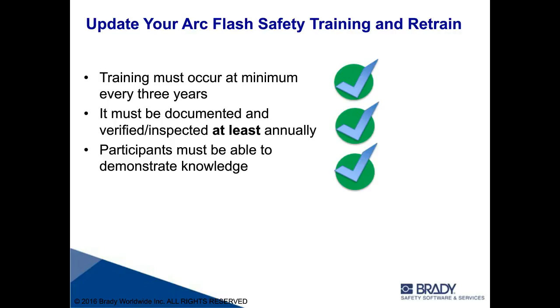Code says training must occur at a minimum of every 3 years. It also says it must be documented, verified, and inspected at least annually. Those annual inspections mean the employer is responsible for auditing their guys, making sure they're doing safe work practices, making sure they're doing lockout tagout correctly. Anytime something is noted that they're not, you've got to address that.